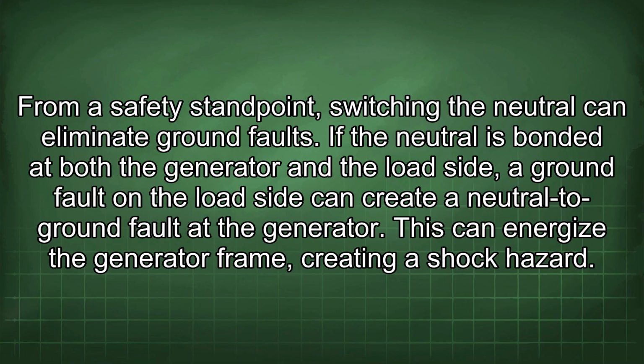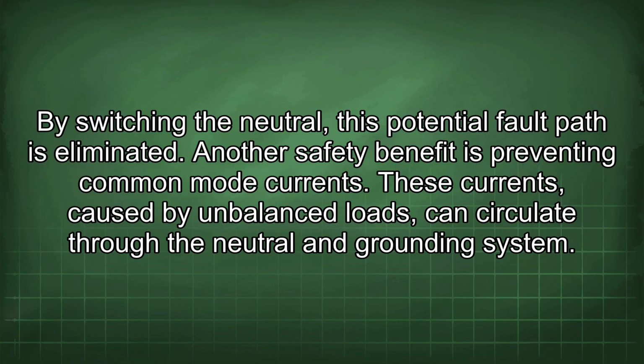If the neutral is bonded at both the generator and the load side, a ground fault on the load side can create a neutral to ground fault at the generator. This can energize the generator frame, creating a shock hazard. By switching the neutral, this potential fault path is eliminated.